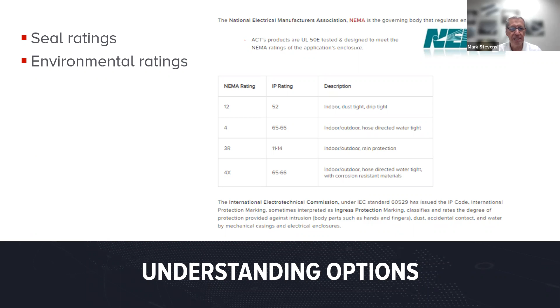We also did some special testing on our HSC lines, our heat sink coolers. We had them tested to the UL50E washdown spray down test. A lot of times as a company, you can self-certify your NEMA 4 or 4X rating, but we actually took the extra step and had UL do the testing. So we've qualified for the 50E rating.